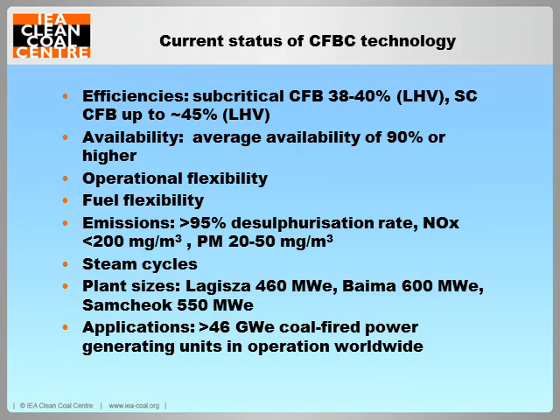A vast majority of existing CFBC units are subcritical with single reheat, which can achieve a plant efficiency of between 38% and 40% based on low heating values. Higher efficiency can be achieved by the emerging supercritical larger CFBC boilers. The world's first supercritical CFBC plant, with a capacity of 460 megawatts electric, has achieved a plant efficiency of 41.6%. It is claimed that modern CFBC power plants can achieve a net plant efficiency of up to 45%.